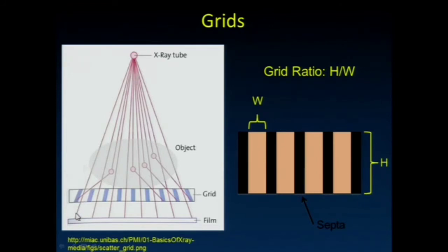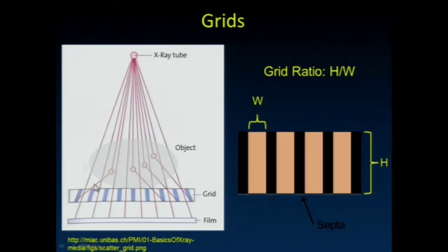Primary x-rays, unchanged in direction, should pass through the holes. Occasionally a primary may strike one of the lead strips and not make it through—so grids reduce primaries as well as scatter. It's just that they reduce scatter much more than they reduce primaries, so the overall scatter-to-primary ratio gets much better.